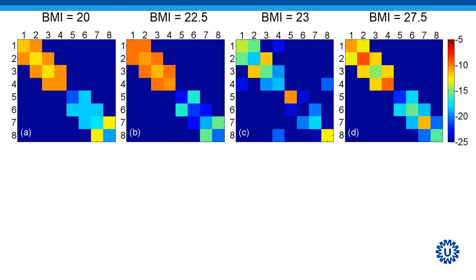We investigated the robustness of the array towards various imaging subjects with widely varying BMI values. You can see from these scatter parameter plots that both reflection and coupling are very acceptable for this wide range of investigated volunteers.